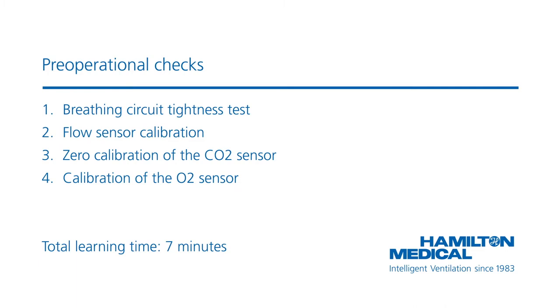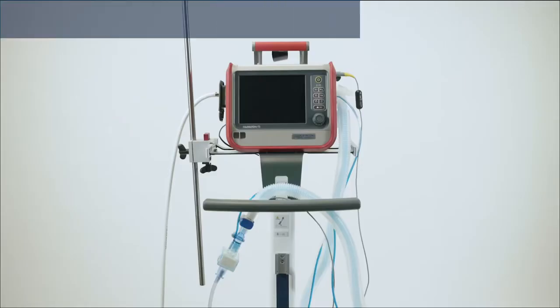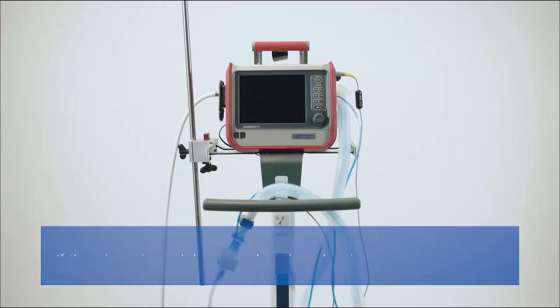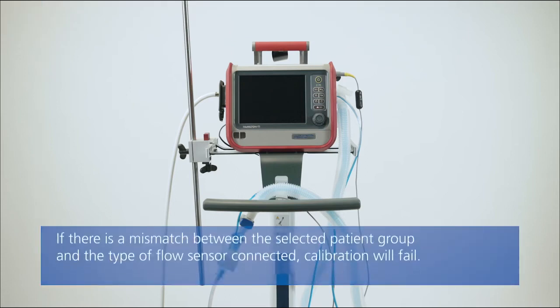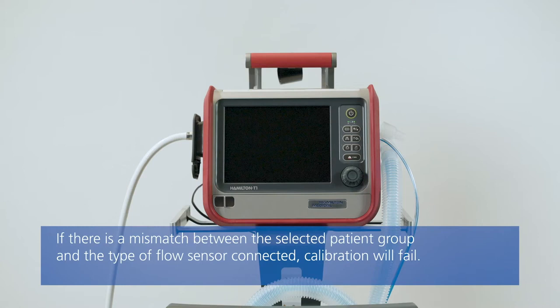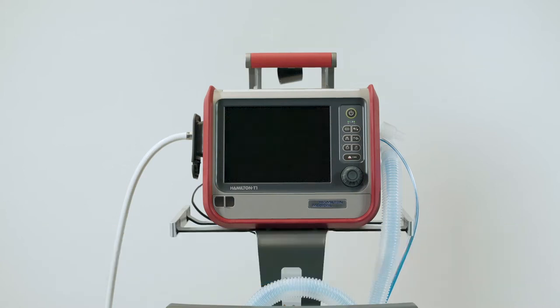Make sure you always do the pre-operational checks before connecting a new patient to the ventilator and after you've connected a new breathing circuit or any other new component. You should be able to complete the whole module in less than 7 minutes. Before starting the pre-op checks, make sure that the ventilator is connected to both primary power and an oxygen supply, that you are using the correct flow sensor for the patient, and that the breathing circuit is assembled correctly.